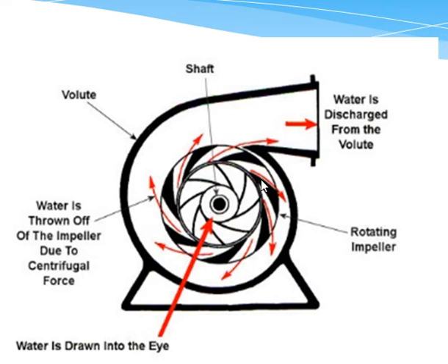It's thrown outward. Now, as this water is thrown outward, that water is sped up. The speed of that water becomes close in velocity to the speed at which the impeller is rotating. So that water is sped up. Now, as that water speeds up, it then hits the casing of this pump, the pump housing on the inside. As that water sort of smashes into that casing, it then slows down.